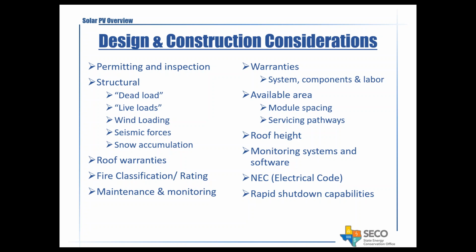Maintenance and monitoring is a big thing. Basically, we have been to facilities, unfortunately, where the systems are in place, but nobody knows what the generation was or if it's working or not, because for one reason or another the monitoring system wasn't working, or the manufacturer who had installed it is no longer in business and they didn't know what to do, and nobody else wanted to go and fix it, basically.